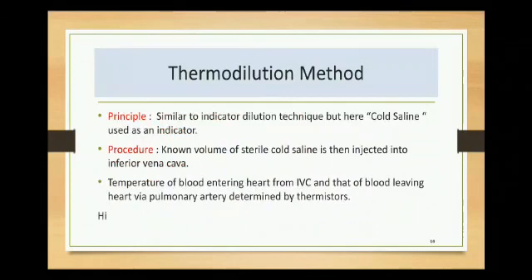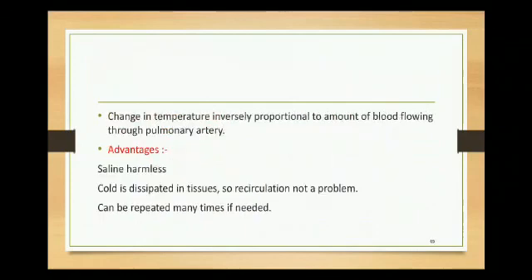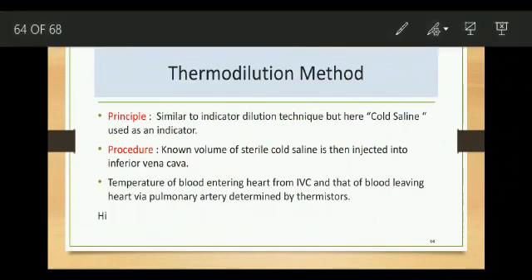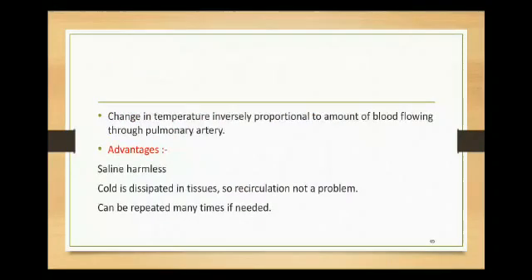The thermodilution method is similar to the indicator dilution technique but uses cold normal saline instead of Evans blue dye. A known volume of sterile cold saline is injected into the inferior vena cava, and the temperature of blood entering the heart from the IVC and leaving via the pulmonary artery is determined using thermistors. The change in temperature is inversely proportional to the amount of blood flowing through the pulmonary artery.